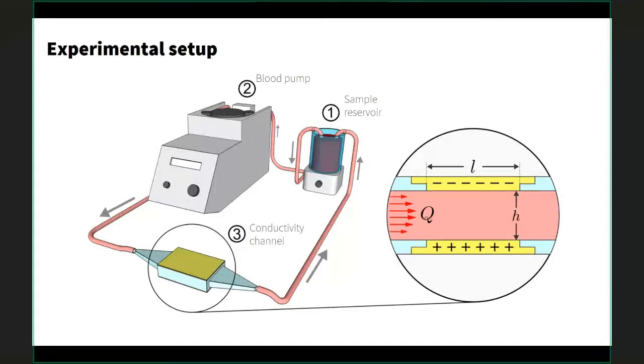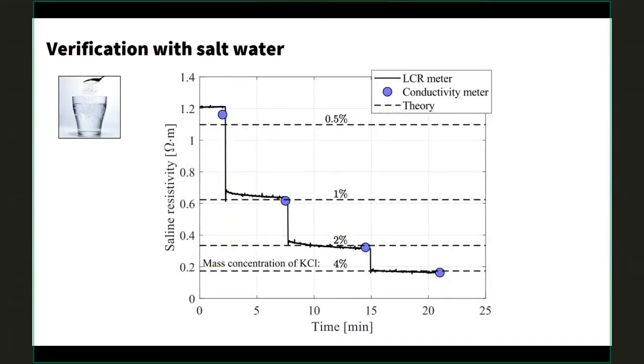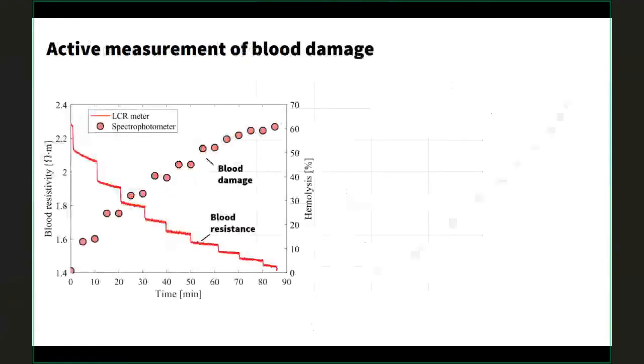We first verified the system using salt water, which has a well-known conductivity-versus-concentration relationship, to confirm we could measure the conductivity of a fluid flowing through our channel. We plotted resistivity — the inverse of conductivity — versus time, and at set intervals added increasing salt concentrations. We saw resistivity drop with each addition as the solution became more conductive. The results matched both a conventional conductivity meter and the theoretical approximation for saline conductivity, confirming the system worked well.